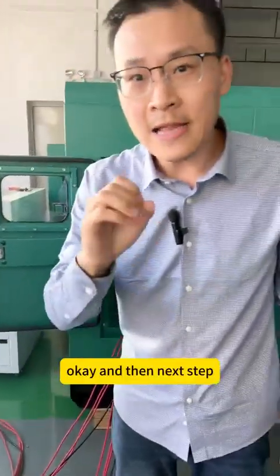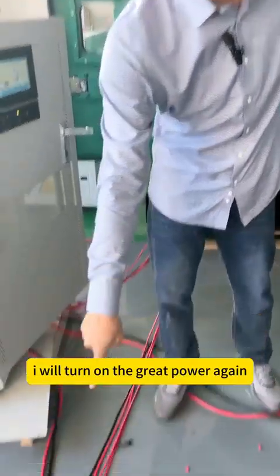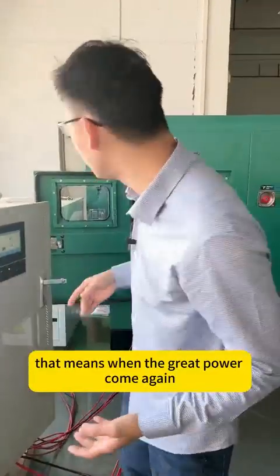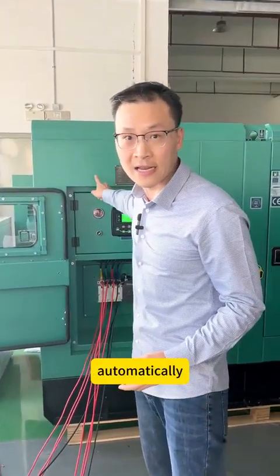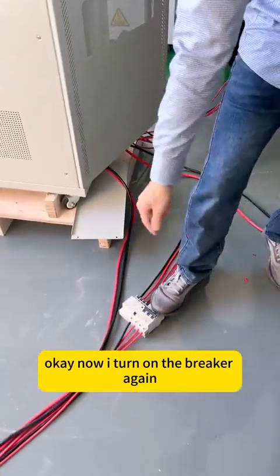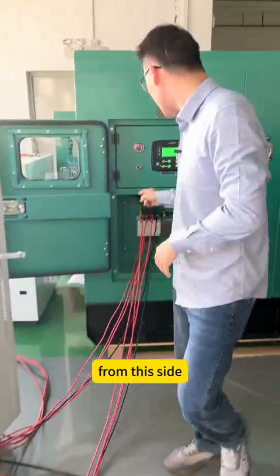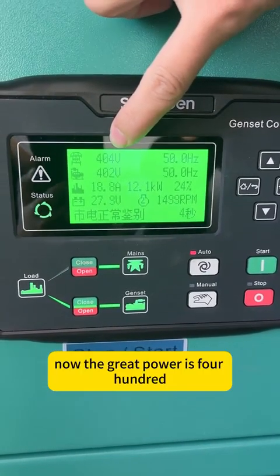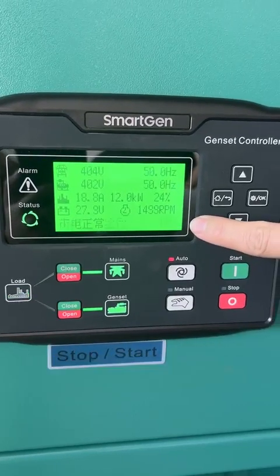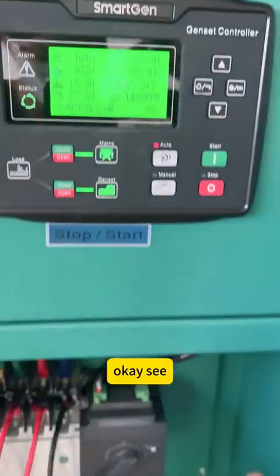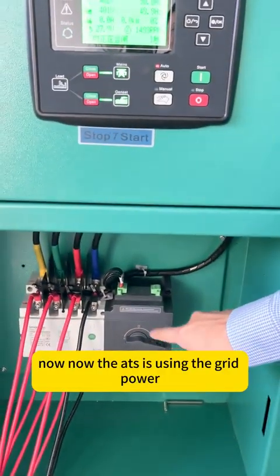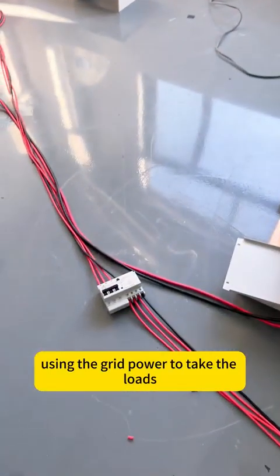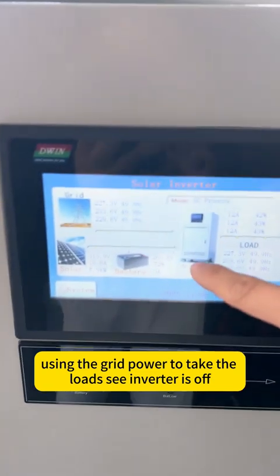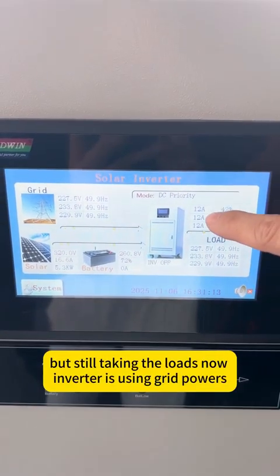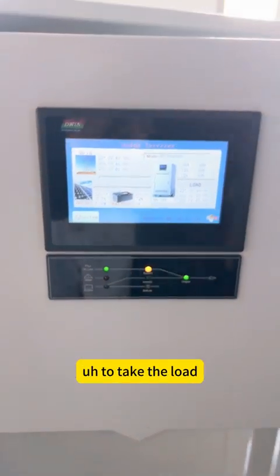Next step, I will turn on the grid power again. That means when the grid power comes again, the diesel generator will turn off automatically. Now I turn on the breaker again, from this side. See, the diesel generator is detecting. Now the grid power is 404 volts. Wait for a few seconds. Now the ATS is using the grid power to take the loads. The inverter is off, but still taking the loads.